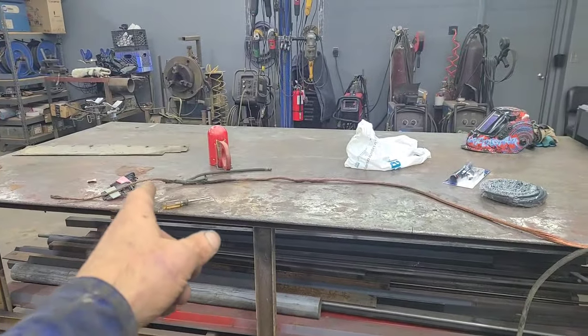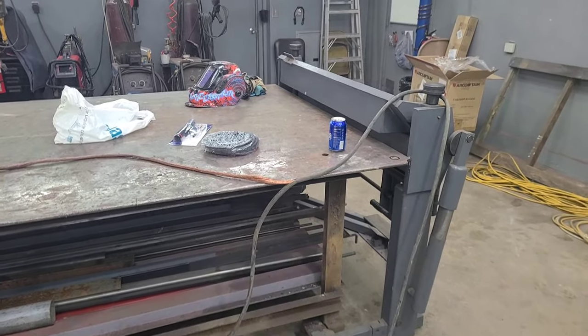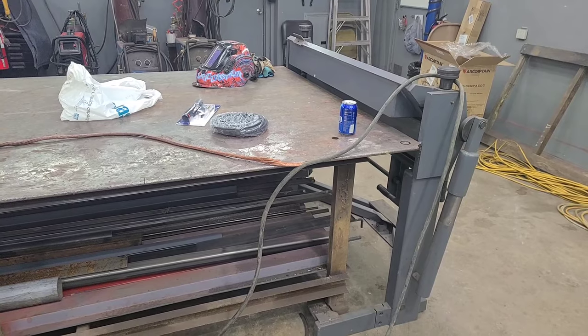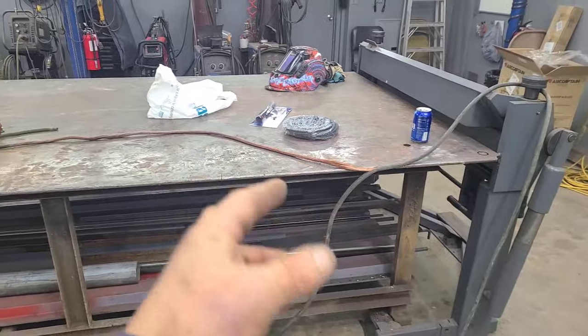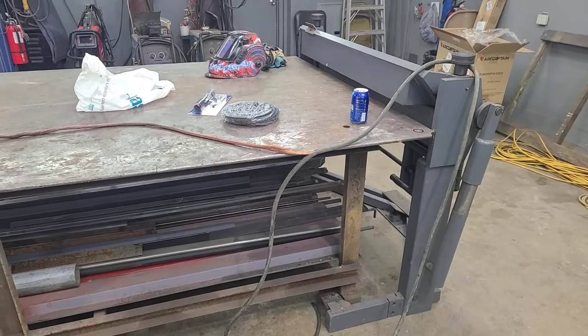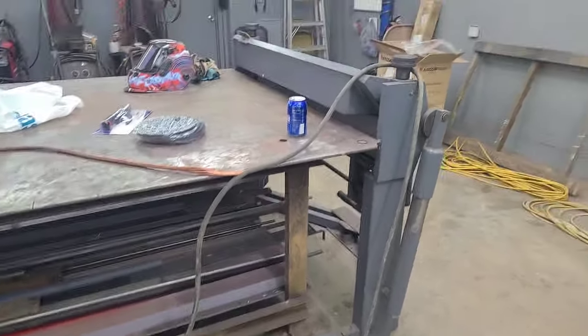Sometimes you might just eliminate, say, 5 to 10 feet of cable and you'll get back to good copper. Other times, if you have to eliminate a lot more, or if you've eliminated 5 or 10 feet several times, you're probably going to want to add some. Don't throw away any of your good copper. Strip it back on each end. See what you've got. If you've got good copper, maybe you can splice some on it or splice some pieces together.